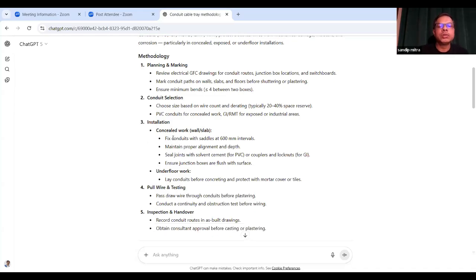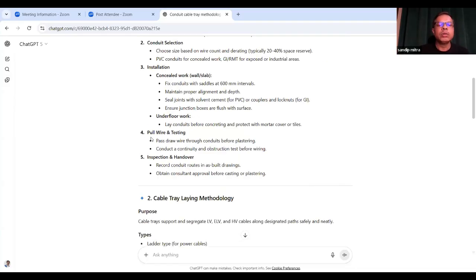Then installation, whether it is concealed, through wall or slab: fix conduit with saddles at 600 mm intervals. So at a 600 mm gap, we have to insert a saddle to fix the conduit, maintain proper alignment, and seal joints with solvent cement or couplers. Ensure junction boxes are flush with the surface, and underfloor work also. Lay conduit before concreting and protect the mortar cover or tiles. After conduiting, you have to pull the wire and do testing.